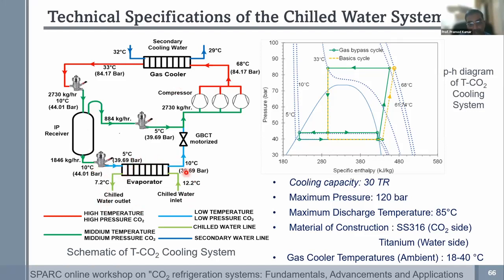across the evaporator. The main advantage of the system is that the cooling is almost instantaneous. Unlike R134A or something where the system has its own inertia, with a carbon dioxide system that inertia is extremely small. The moment you turn on the system, you will find that it starts producing cooling.